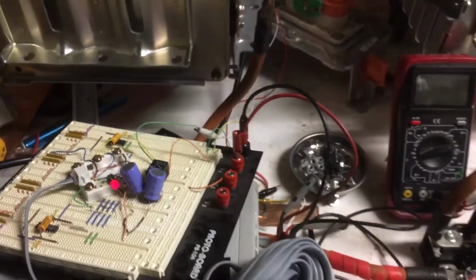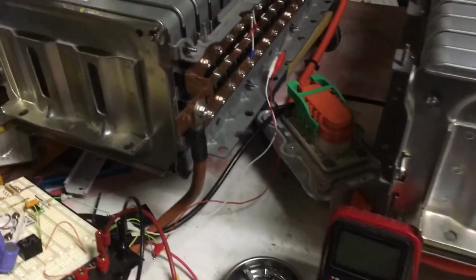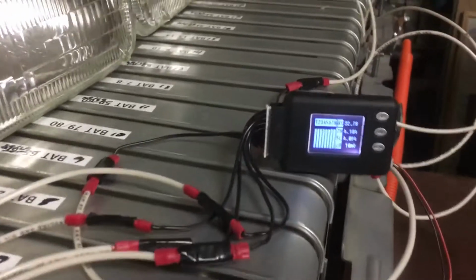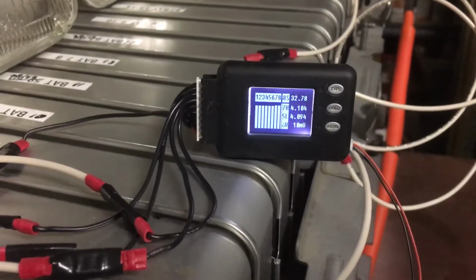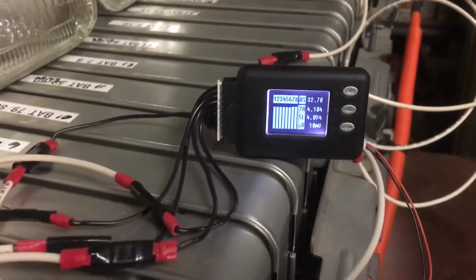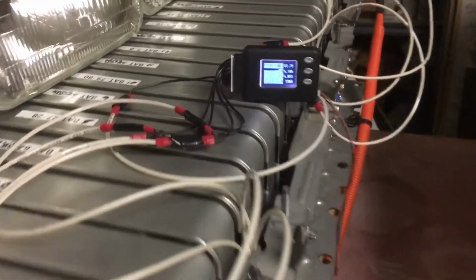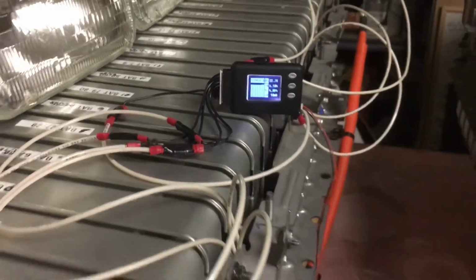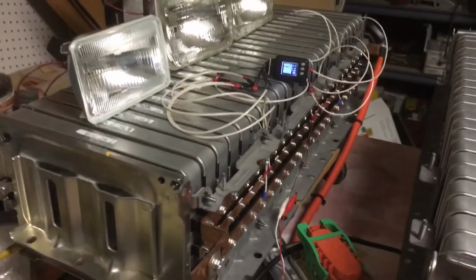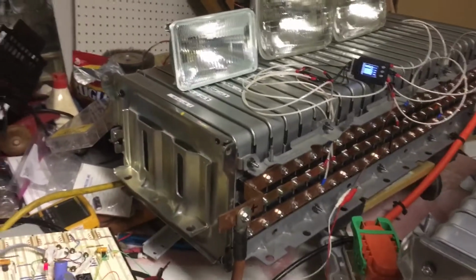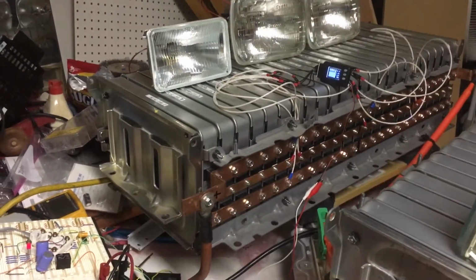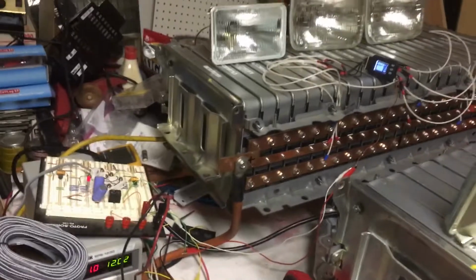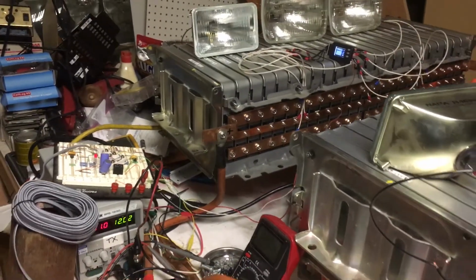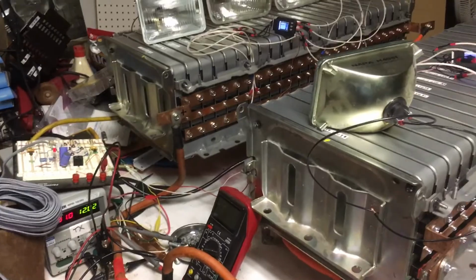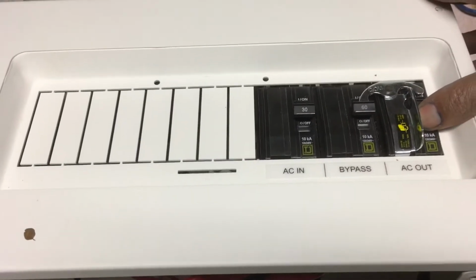So I was going to try and demo that for you. Let's see how that goes. The batteries are fairly charged up, so you can see the half pack voltage here is at 32.78. I've set the alarm for that to 32.6, which is much higher than I normally would, but that should get a fairly quick action, especially because that voltage will sag 100 millivolts or so once I engage the draw on the inverter. So all I need to do is turn on my AC out breaker.